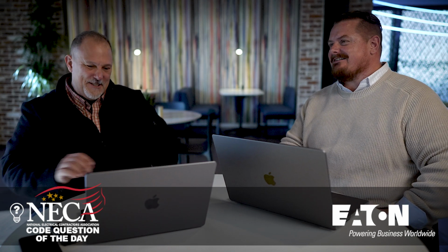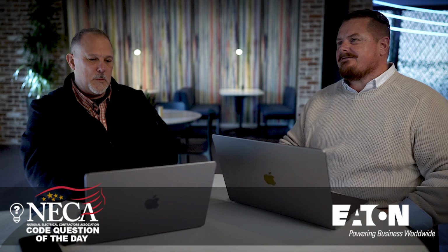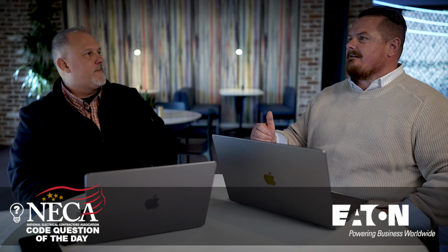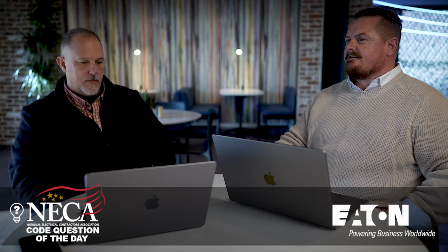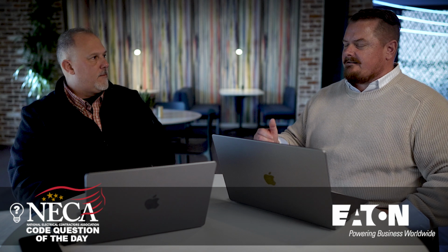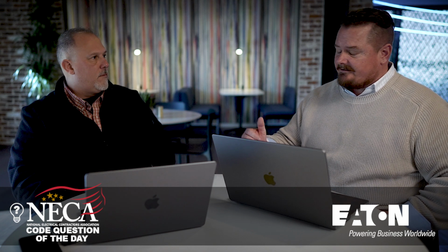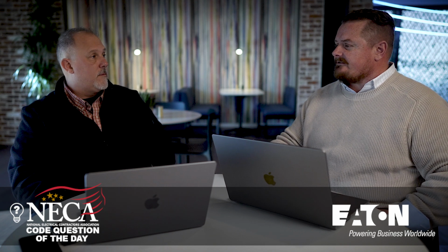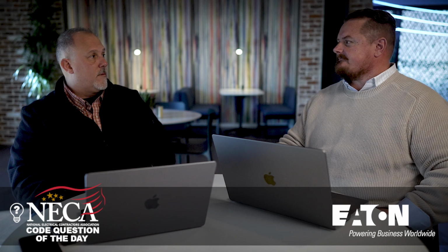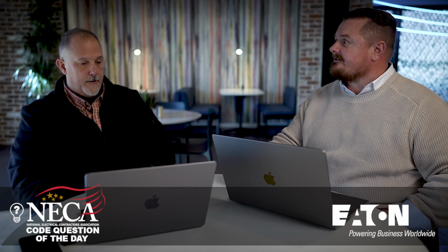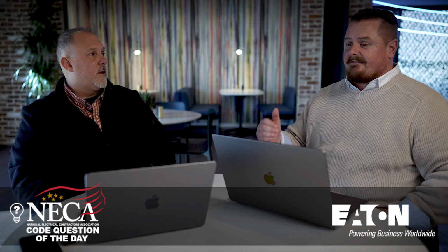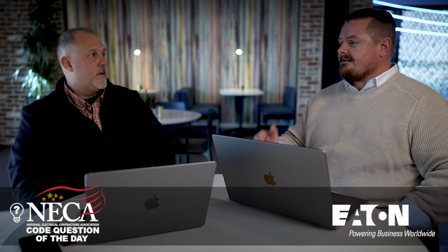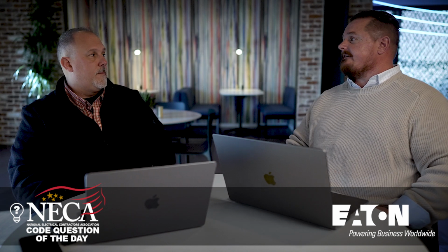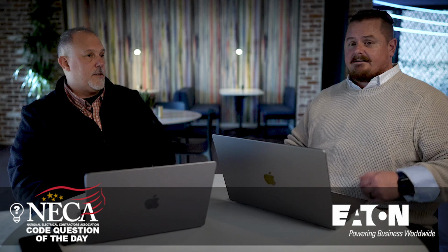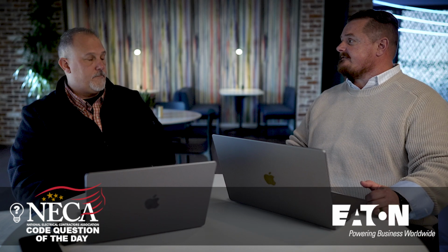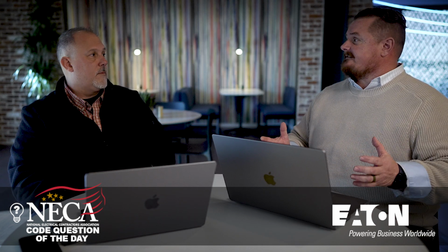It's in the field. So if we look at those two requirements, it really drives the idea that on a new installation, there should be documentation somewhere. Sure. A short circuit current study or an evaluation of some sort that is on file, that the AHJ should have access to. Absolutely. The electrical contractor should have access to, and confirm these things ahead of time.